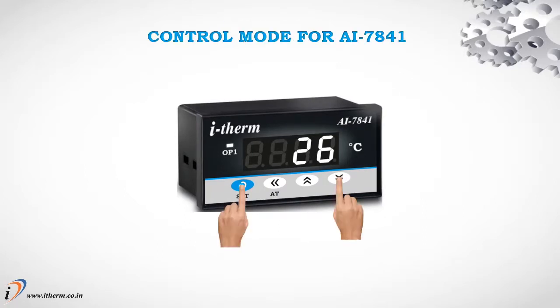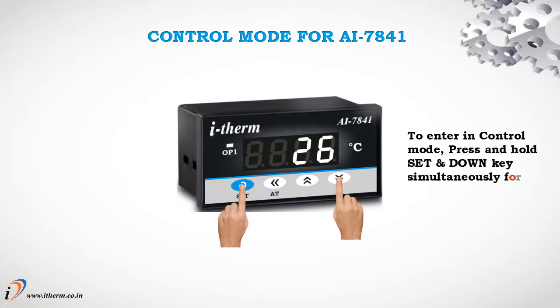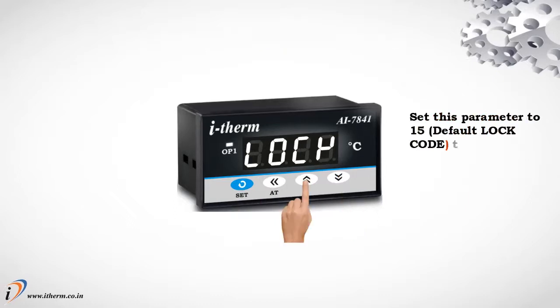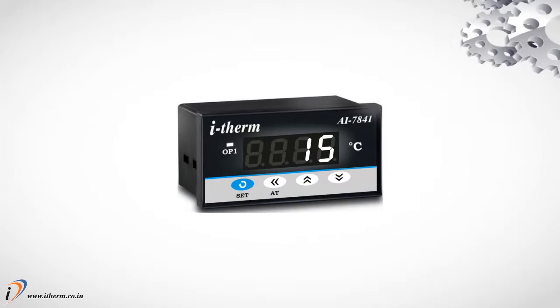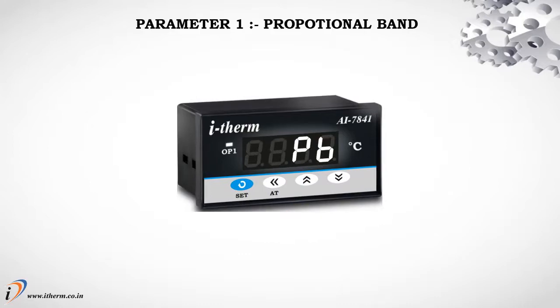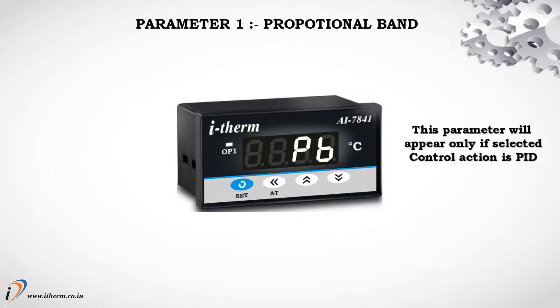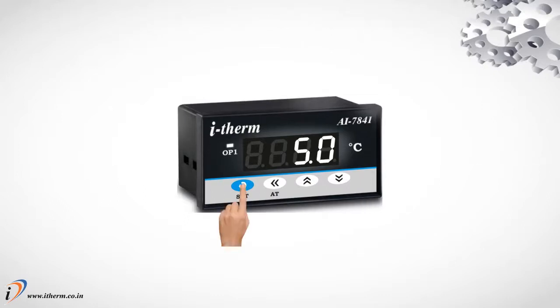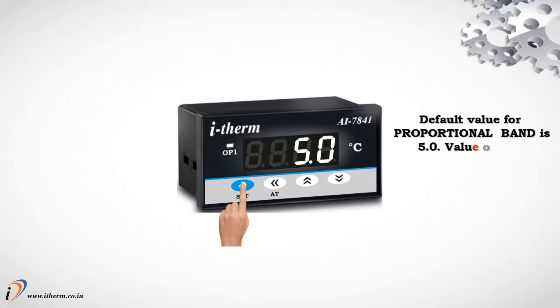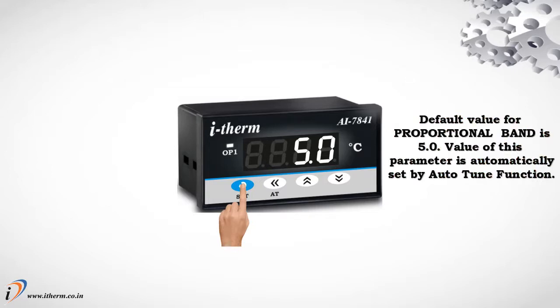Control mode for AI7841. To enter in control mode, press and hold Set and Down key simultaneously for 3 seconds. Set this parameter to 15 to access control list. Parameter 1, Proportional band. This parameter will appear only if selected control action is PID. Default value for proportional band is 5.0. Value of this parameter is automatically set by auto-tune function.